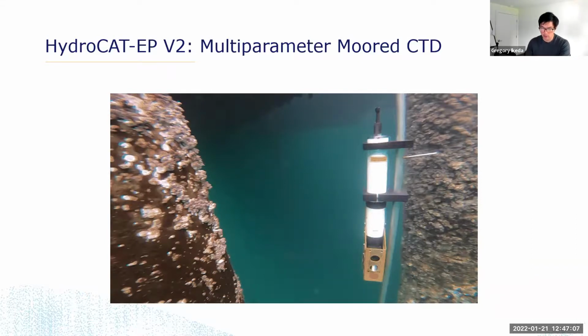But we have published drift specifications that are actually pretty conservative. I can pull up, I think, the data sheets. I don't have that handy, unfortunately. But yes, I would say that for every sensor from Seabird, we have very carefully characterized the drift specifications. So depending on the accuracy that you need from your instruments, you can calculate how long you might leave it out there before recalibration. For the HydroCAT-EP V2, I will warn you that the pH sensor uses this glass electrode technology that I'd say 99% of all pH sensors utilize. And so that needs to be recalibrated every 90 days in order to maintain the accuracy spec. So that's really the limiting factor of your sensor's deployment in terms of data accuracy.